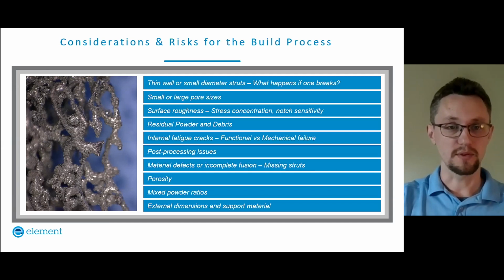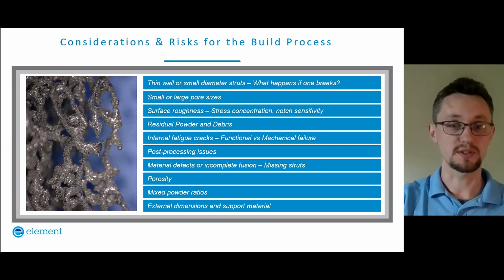A lot of these will have small or large pore sizes that need to be considered. We've talked a little bit about surface roughness. Anytime you have roughness, you're going to have a stress concentration you have to consider, notch sensitivity. That might be okay here on this strut, but it might not be okay here, on a much, much smaller one. You have to think about residual powder and debris. You also need to think about internal fatigue cracks.